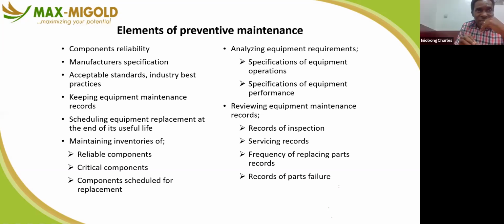So this kind of maintenance is mainly about looking at the failure mode of that particular thing, how it works, before you deploy this kind of maintenance. It's mainly for small things like your light bulb. You can't put scheduled preventive maintenance around a light bulb or a printer. Even your borehole, even your pumps, the highest you can do is put a backup there. You can't say every month I'm going to check the pump, loosen it, open it up, clean it. You won't do that. So the best you can do is put a backup. When that one fails, you replace it with the backup, take the faulty one out, fix it, and bring it back. So it's a strategy deployed based on the facility you are managing.